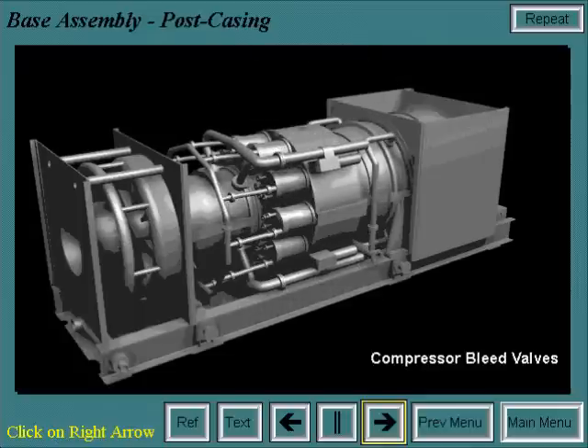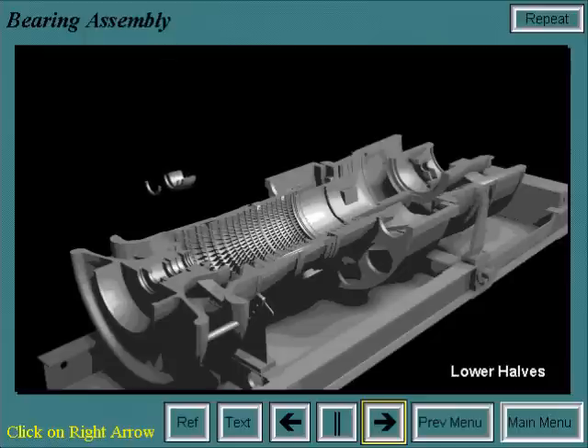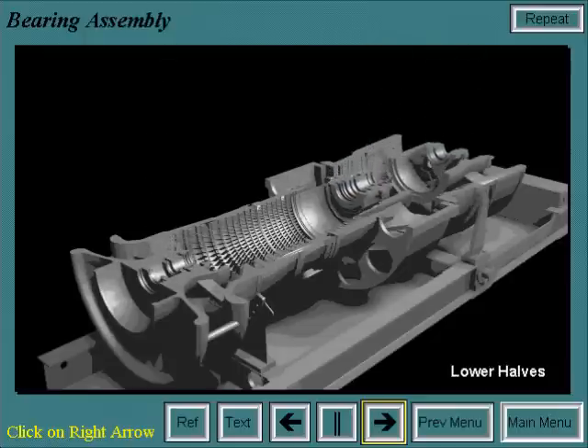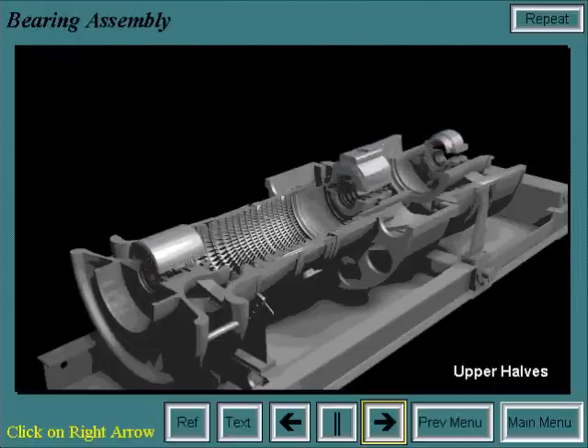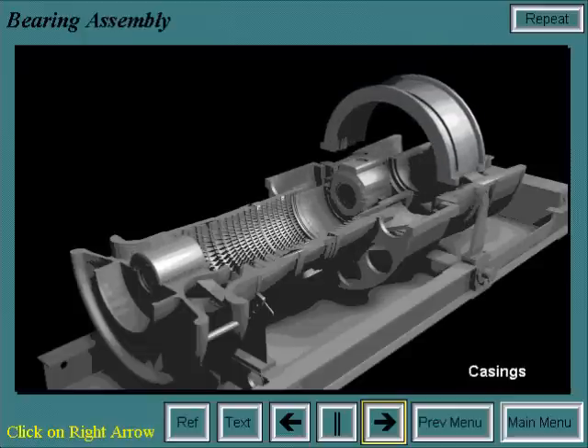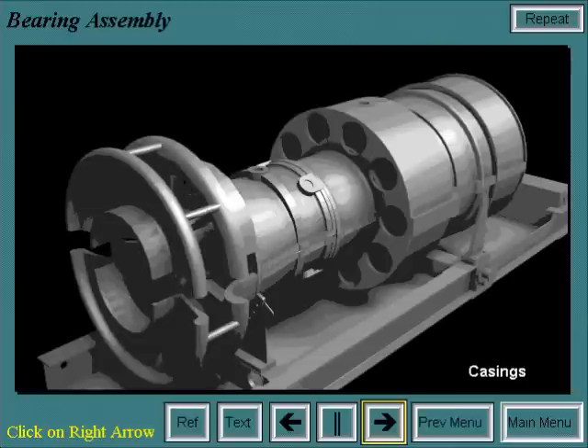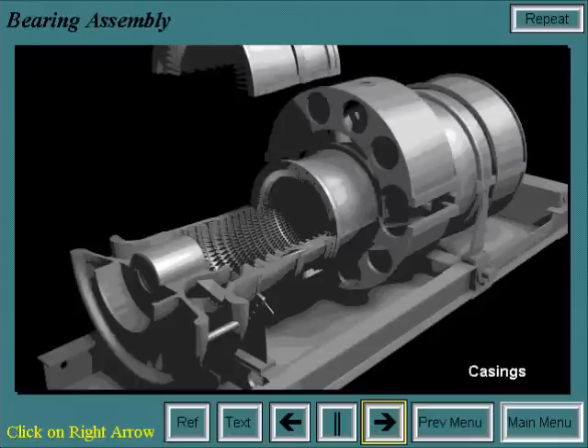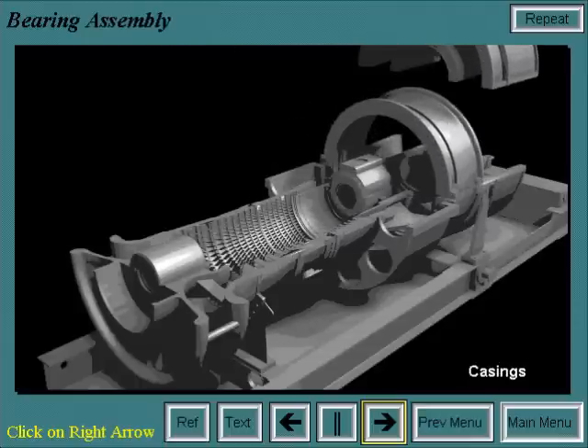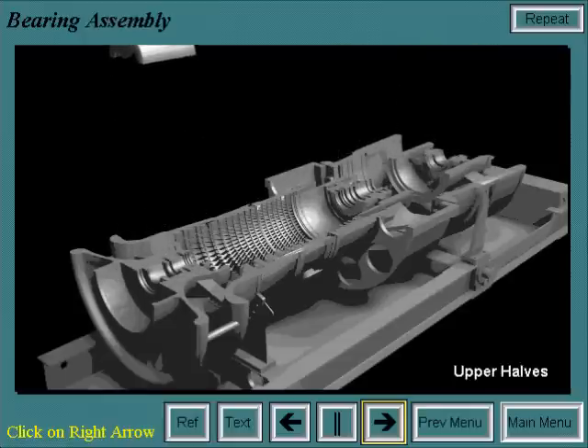These bleed valves are operational during start-up and shut-down to protect the unit from surge. The number one bearing is installed in the inlet casing, and the number two and number three bearings and housings are placed into their respective casings. The lower half is put in first, then the upper half of the bearings and housings are installed. Then the bearings are aligned with the casings installed. The upper halves of the bearing housings and casings are then removed and the air seals and oil deflectors are installed.